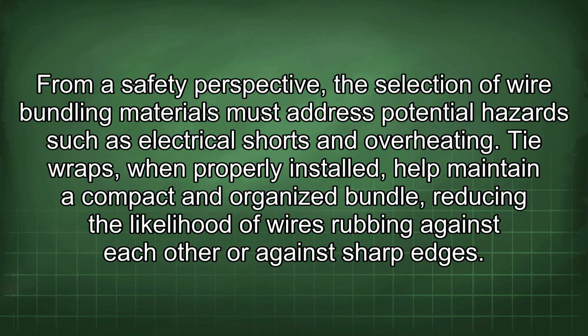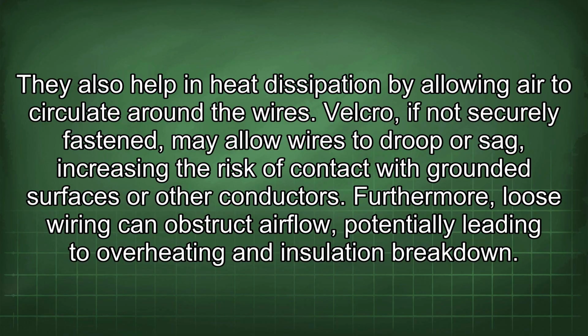From a safety perspective, the selection of wire bundling materials must address potential hazards such as electrical shorts and overheating. Tie wraps, when properly installed, help maintain a compact and organized bundle, reducing the likelihood of wires rubbing against each other or against sharp edges. They also help in heat dissipation by allowing air to circulate around the wires. Velcro, if not securely fastened, may allow wires to droop or sag, increasing the risk of contact with grounded surfaces or other conductors. Furthermore, loose wiring can obstruct airflow, potentially leading to overheating and insulation breakdown.